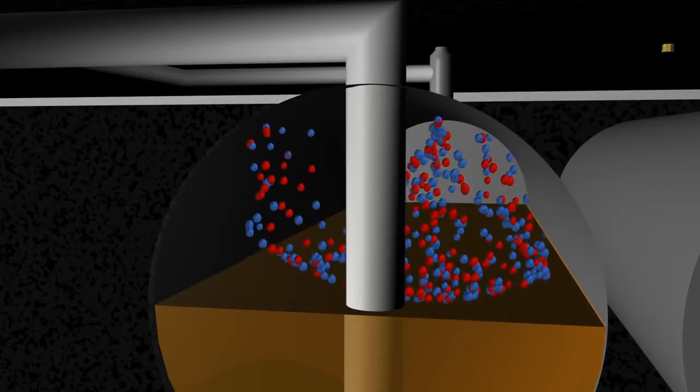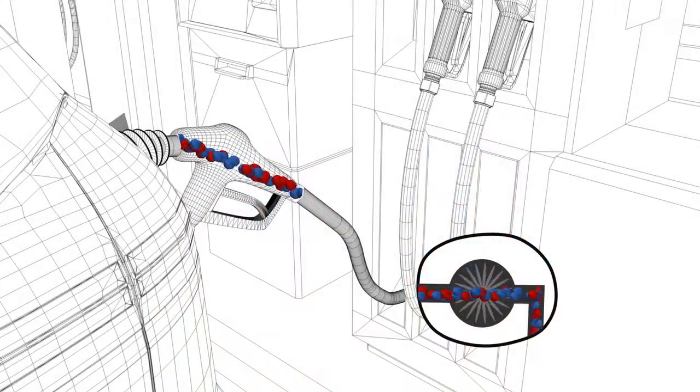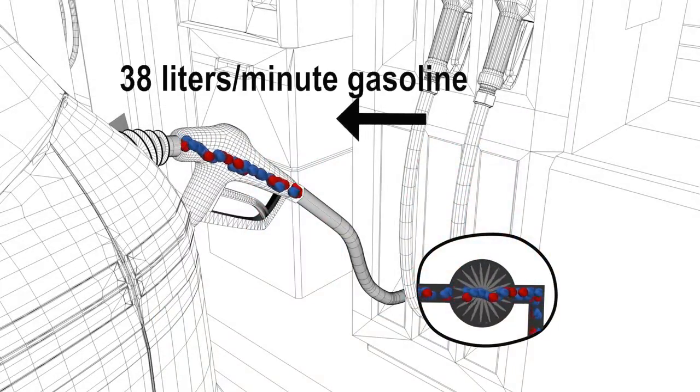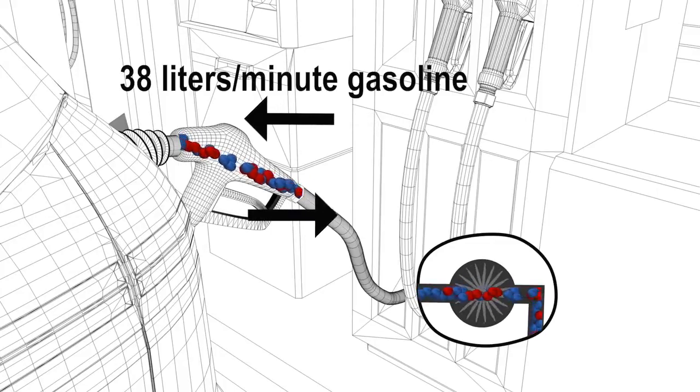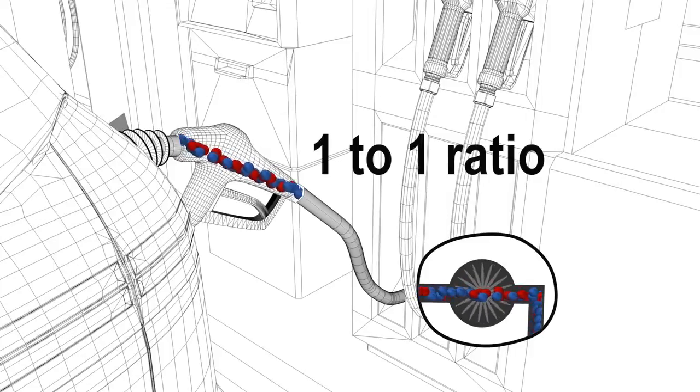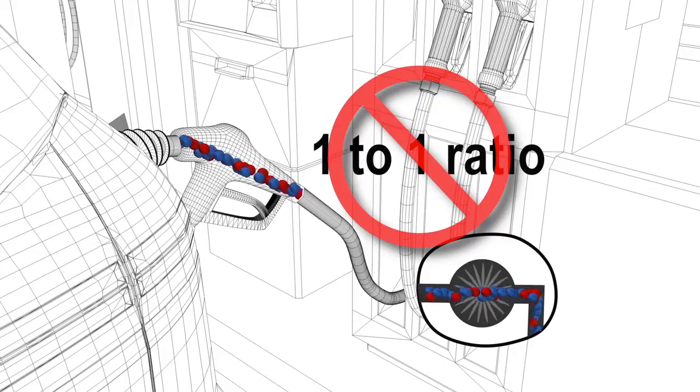The volume of vapor collected is set manually and is based on how the system is calibrated. For example, if the fuel dispenser is set to deliver 38 liters of gasoline per minute, the stage 2 pump can be set to draw in 38 liters per minute of the vapor mixture. In other words, a 1 to 1 ratio. However, the use of a fixed ratio is based on the incorrect assumption that an equal volume of vapor mixture is generated. Here is why this assumption is incorrect.